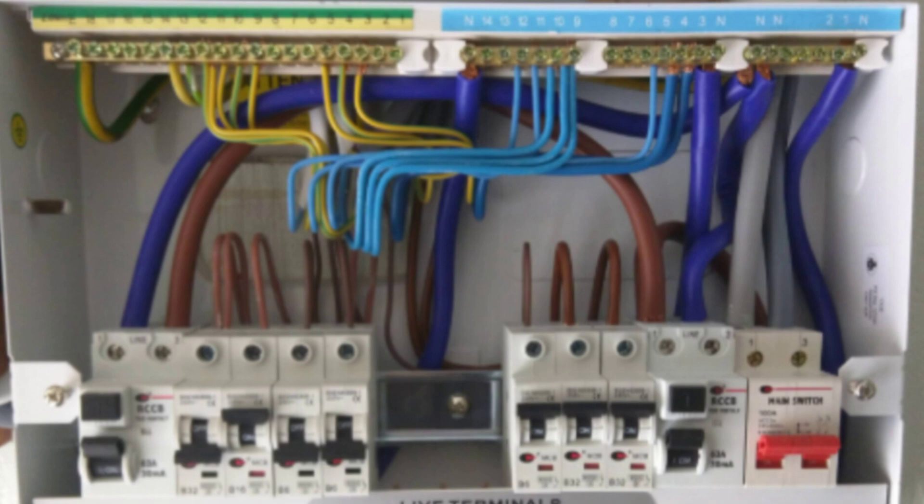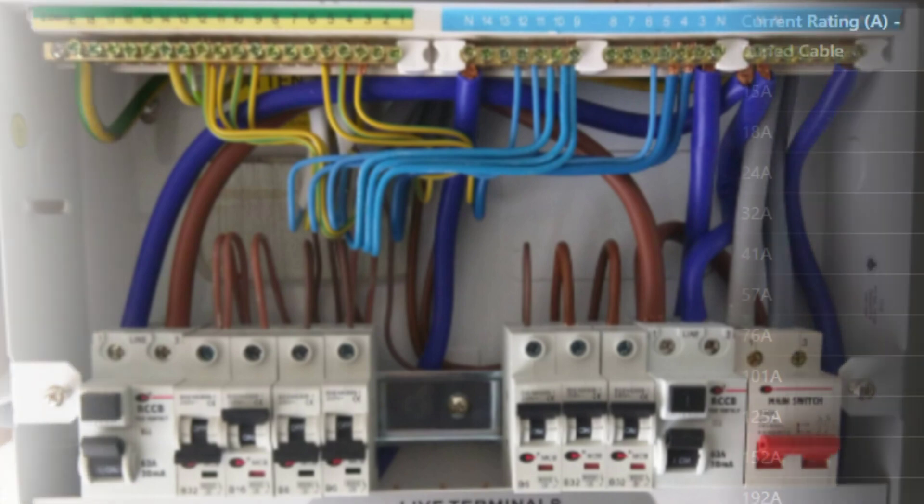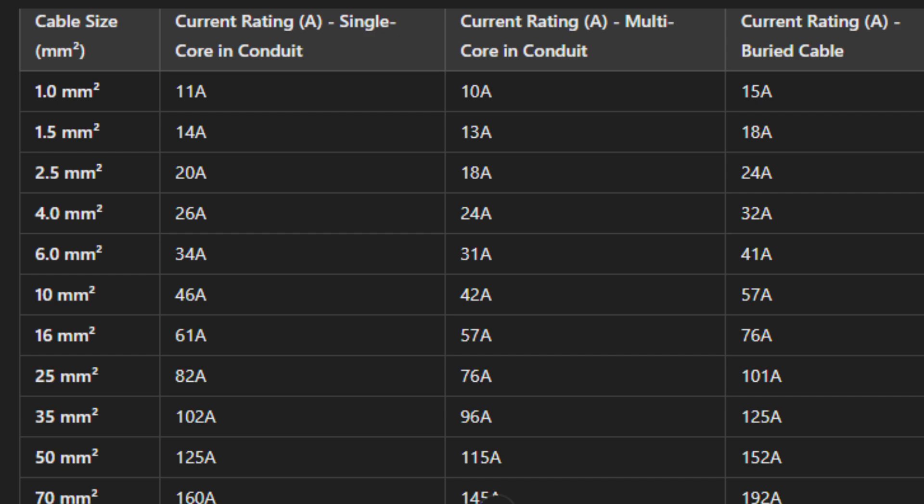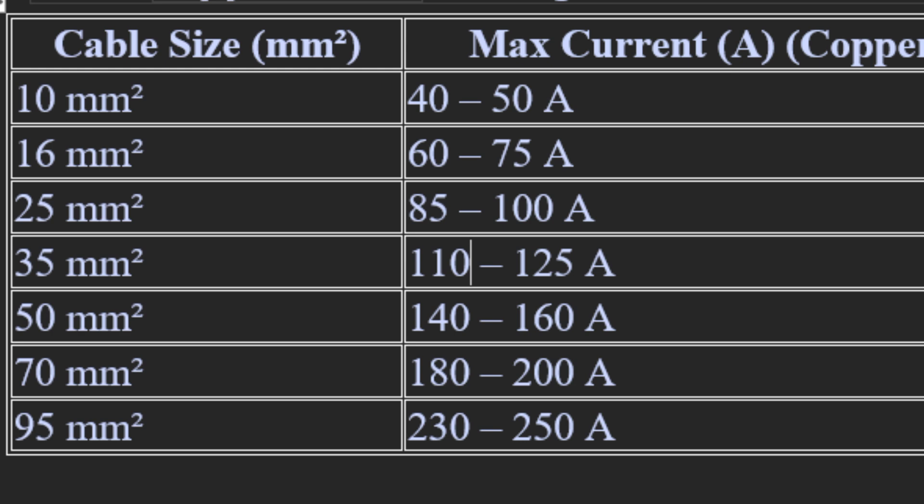After getting the current, we move on to choose the cable size based on the current rating. We refer to either a cable manufacturer's table or standard charts. Most cable manufacturers have a table showing cable size and the maximum current it can carry. You can also reference standard charts from the IEC, NEC, or BS 7671. For example, a 10 millimeter squared cable can carry between 40 to 50 amps — this variation accounts for cable quality and ambient temperature. It is best to refer to the cable manufacturer's table.